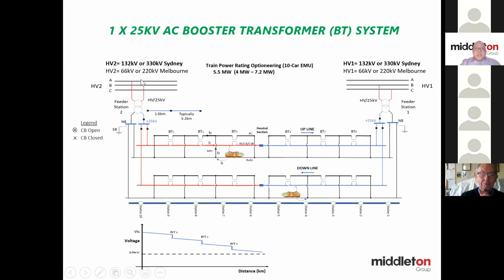And again, the HV connections are very similar, but with the booster at 3.2 kilometer intervals. And again, you need a neutral section. So if you're using boosters to feed the supply of 5.5 megawatt trains in a 24 trains per hour per direction formation to meet your timetable, you will most certainly need to feed from both ends of the tunnel.